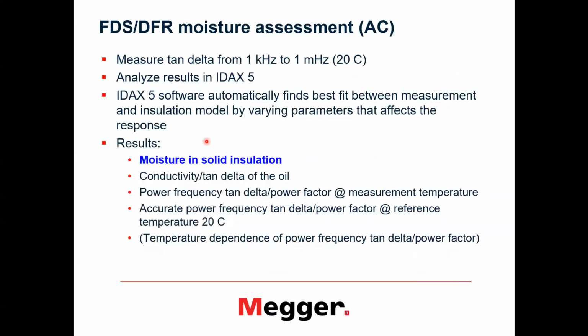So in order to assess moisture by using the dielectric frequency response, we measure tangent delta from 1 kilohertz to 1 millihertz. Well, we can do it at 20 degrees, or if it is done at different temperatures, then there is a temperature correction, not using tables, but using measured data to correct to 20 degrees. Then in the IDAX software, we analyze this measurement, and it will give us the results in terms of moisture in solid insulation, conductivity, tangent delta of the oil, and also power factor at measurement temperature and power factor at reference temperature.